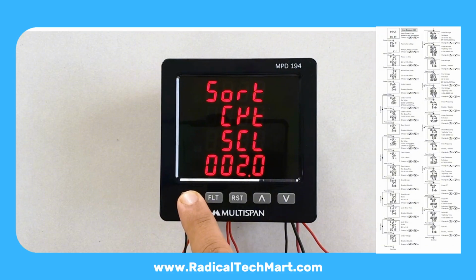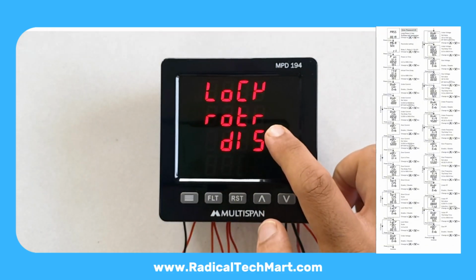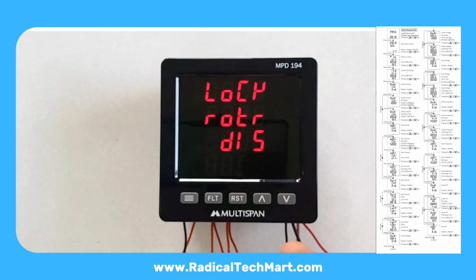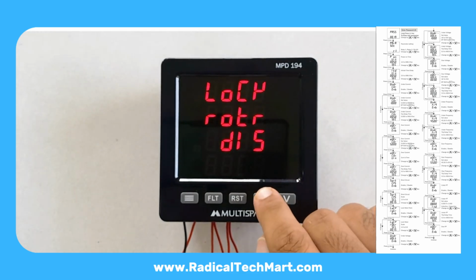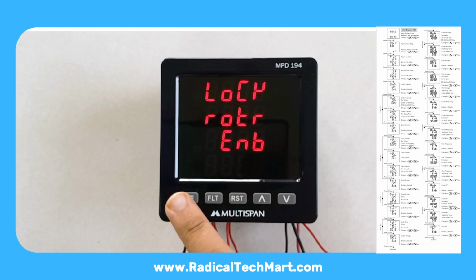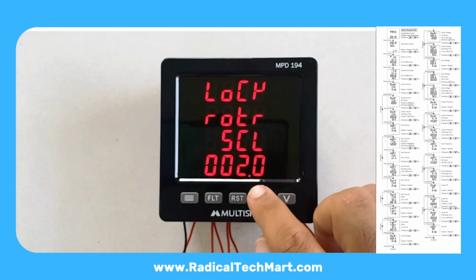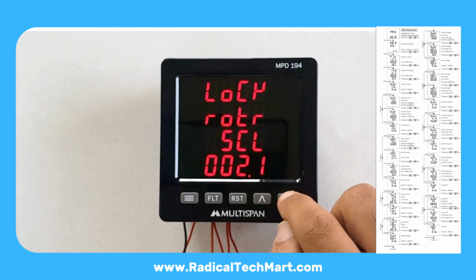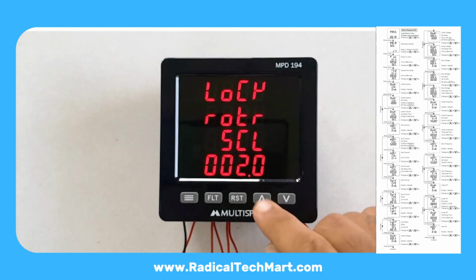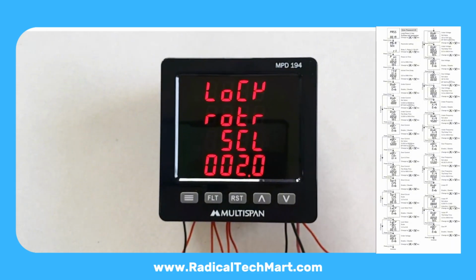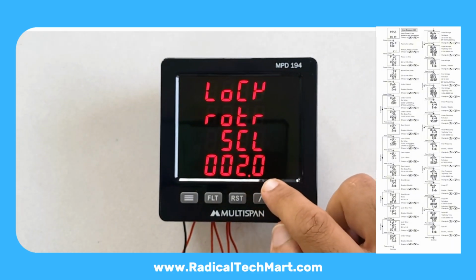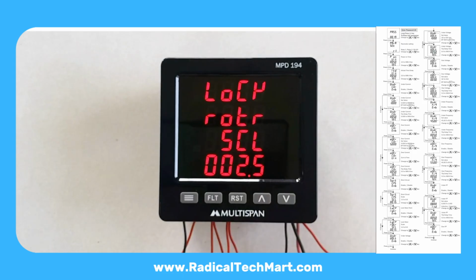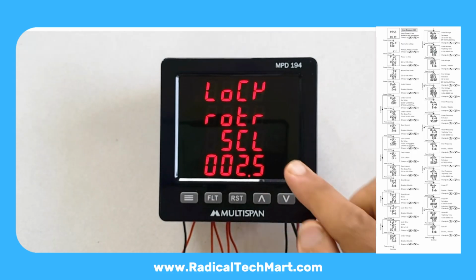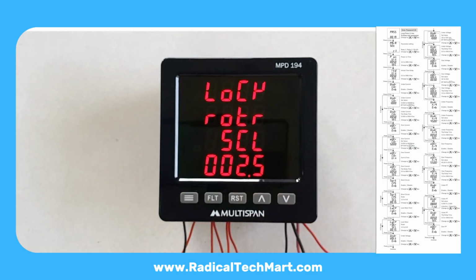Press Set. Enable or disable locked rotor protection. This is used when the rotor and stator get jammed and the current stays very high. You set a scale factor in decimal. Example: overcurrent setting is equal to 10 amperes. Locked rotor scale is equal to 2.5. Then locked rotor threshold is equal to 10 times 2.5 is equal to 25 amperes. If current goes above 25 amperes, the relay trips instantaneously and the display will show locked rotor trip.